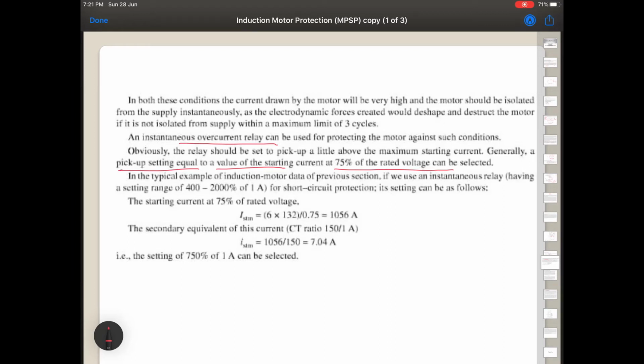So if the relay is set for 4 to 20 times the rated current, then at 75% of the rated voltage, the starting current of the induction motor is always 6 times the rated current. And since it is set at 75% of the rated voltage, 0.75 is divided into it and we get this answer. Now you may get a question why we are dividing it by 0.75.